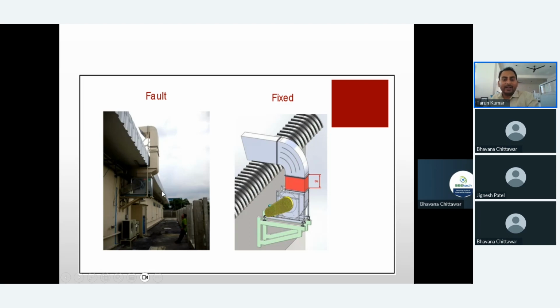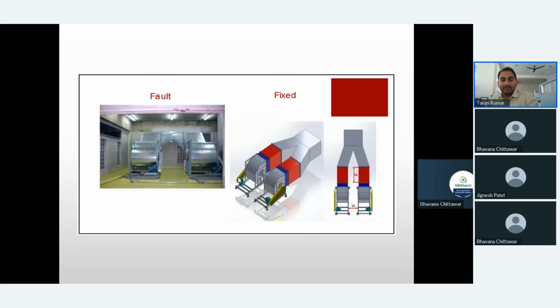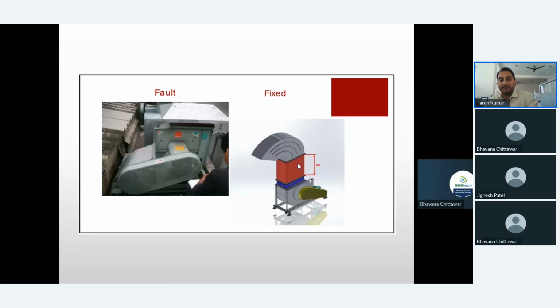They would have taken that fan a little bit outside, and they would have taken this kind of arrangement, which will avoid the bend as well as the back pressure over the fan. Again, you can see the example of the branches. When you are combining two fans in a single duct, you have to go with some flexible connection, and when you are putting the common duct plenum, you have to go for a certain distance of straight duct, and then go for the branches.